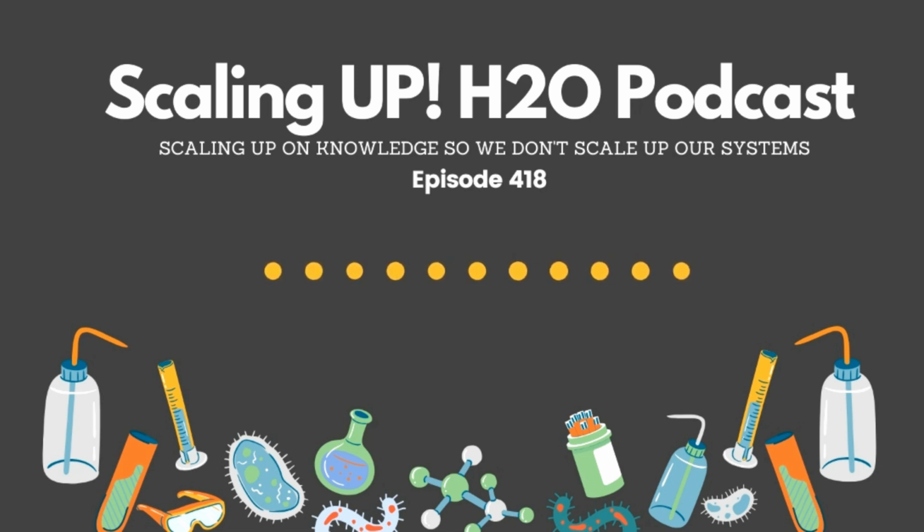From a results point of view, I think dosage is very important. The tendency of a lot of people is to underfeed these materials. And I don't think you can necessarily do that. I think at a minimum, you need 5 to 10 ppm active of these types of materials. And so you can definitely see a correlation between dosage and corrosion rates. Where we've seen some applications less than 5 ppm active, we've seen corrosion rates that have not been off the charts, but been 4 or 5 mils per year. And so it's critical to titrate, if you will, the corrosion inhibitor to the rate that you're expecting.